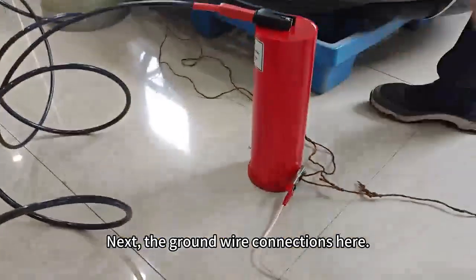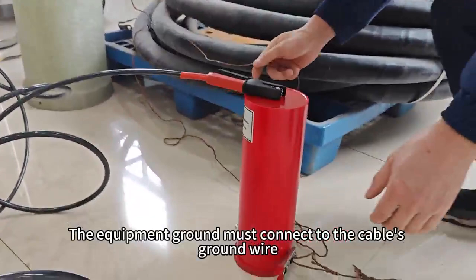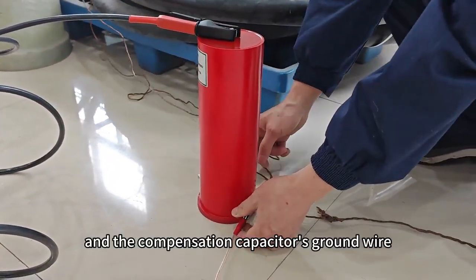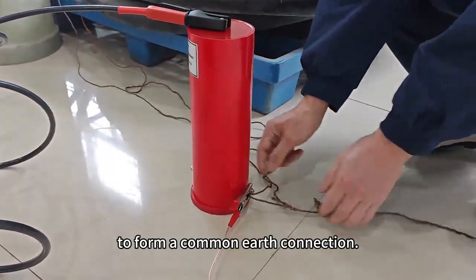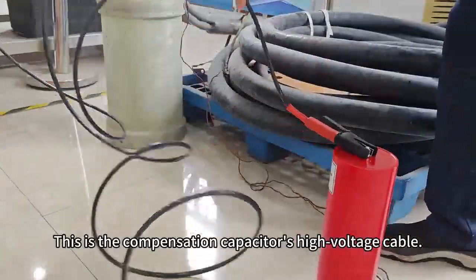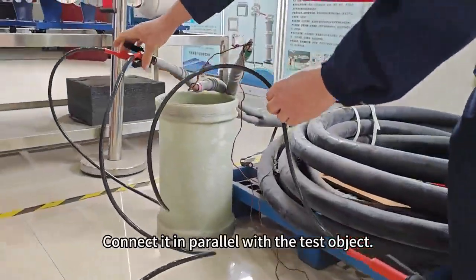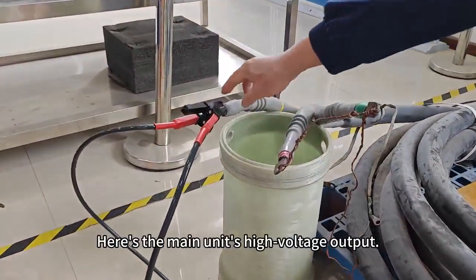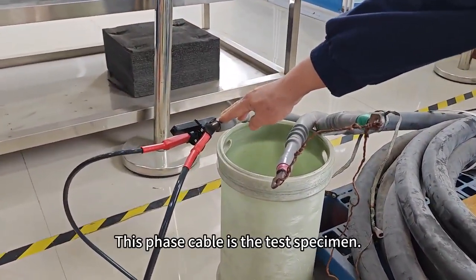Next, the ground wire connections here. The equipment ground must connect to the cable's ground wire, and the compensation capacitor's ground wire, to form a common earth connection. This is the compensation capacitor's high voltage cable, connected in parallel with the test object. Here's the main unit's high voltage output. This phase cable is the test specimen.